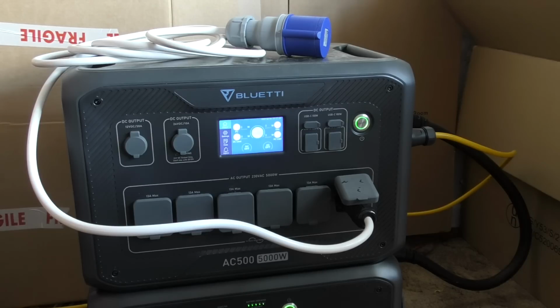That involves quite a lot of work, rewiring and so on. For just an occasional thing, I wanted to try and find the cheapest reasonable way of doing this. So basically the way I wanted to do this was just have a changeover switch on the feed into the distribution board that could just switch between grid and backup, and obviously just not use any of the high loads during the time the backup supply is running.